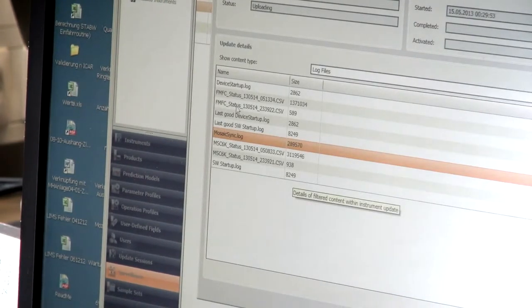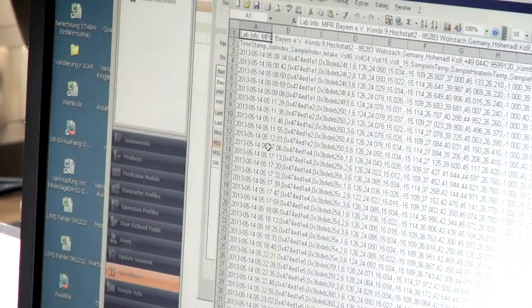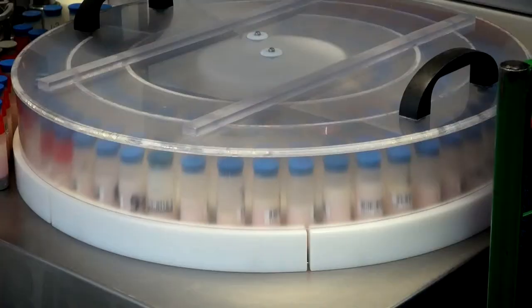In Mosaic we have log files — instrument status log files — showing what's going on with temperature, accu-times, and so on. Those log files are in Mosaic and we can export them to Excel and make graphs. I hope future versions of Mosaic will generate those graphs automatically.